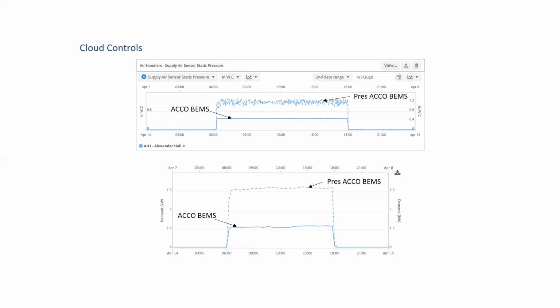And of course, you normalize for downstream data and everything else. One of the big reasons is that ACCO BEMS, the cloud, is looking at a number of variables, including how the downstream VAVs are doing, outside ambient temperatures, and many other variables. What that translates to is the bottom trend, where we're looking at the kW. This is an air handler that's sub-metered. In the solid line, this air handler is running at 2.5 kW versus about 7.5 kW before. So the energy savings are significant. Next slide, please.